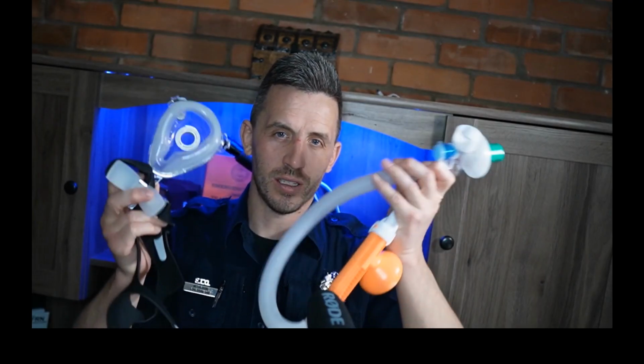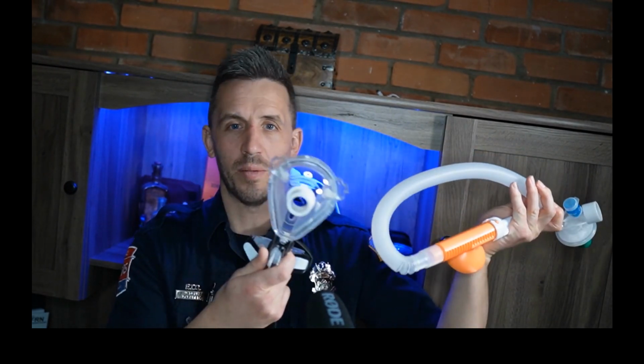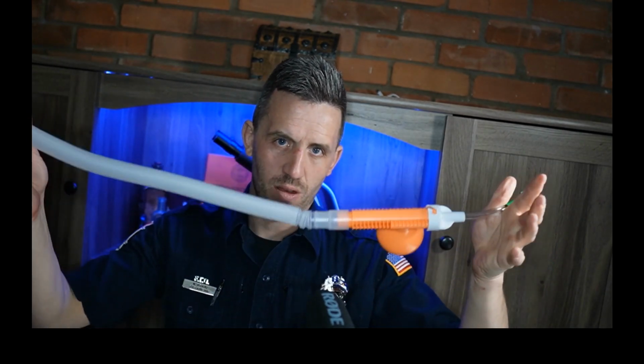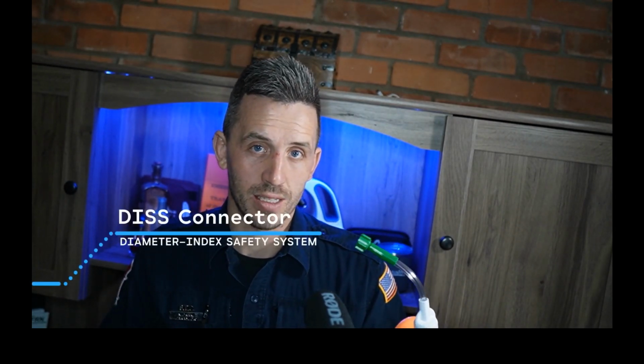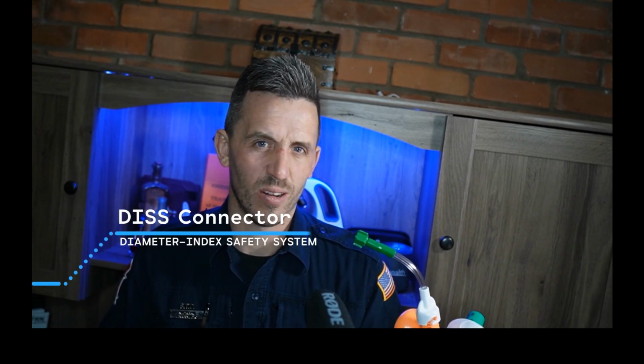So some key things with our CPAP setup. This is our standard setup. Now, granted, they may look a little bit different over time depending on what manufacturer we're using and what's available. But more or less, they all work exactly the same. Starting at this end, this is called a DISS connector, which is a diameter index safety system. It's just a standard thread size and count for hooking up to oxygen supplies for medical gas. The DISS connector is going to be made of plastic.